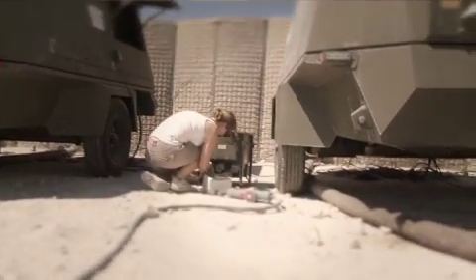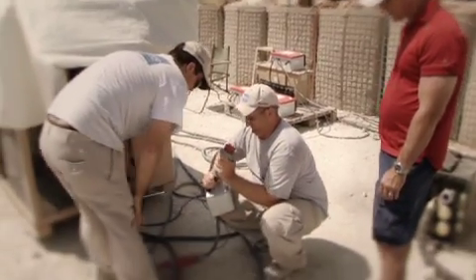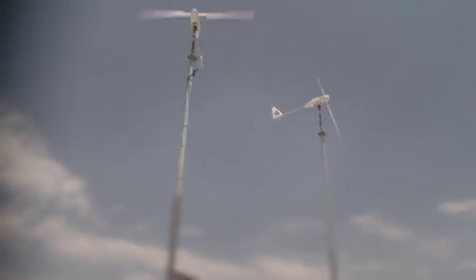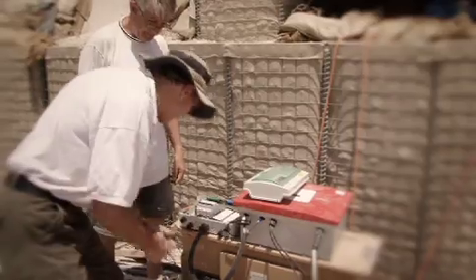The third thing is to use the generators more efficiently — being able to start them and stop them. Starting them automatically from an energy management system has never been done before with these generators, certainly not in the UK, and we've achieved that over this trial. That's going to be really beneficial. You put all those together and that gives you a good baseline and an architecture to work with. Should you wish to add renewables, you can add those in as you wish — wind turbines, photovoltaics, and local sensors for scavenged energy.